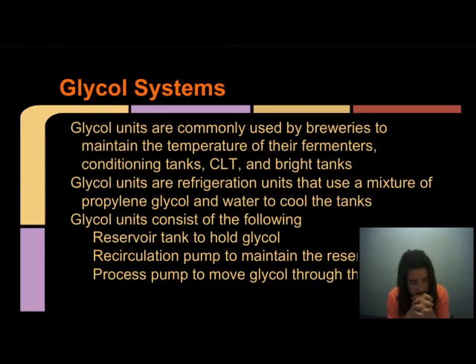So, glycol units consist of a few things. There's the reservoir for the tank that holds the glycol itself. There's the recirculation pump to maintain the reservoir temperature, so it pumps it through the cooling system and keeps it cold. And then there's your process pump that moves the glycol from the reservoir through the actual glycol system and then back.